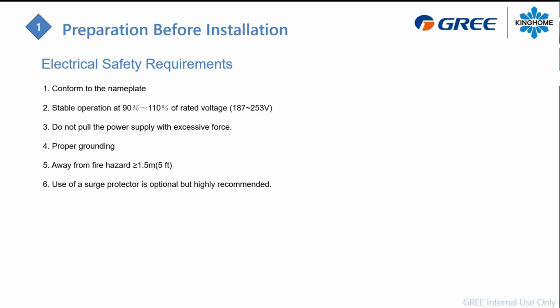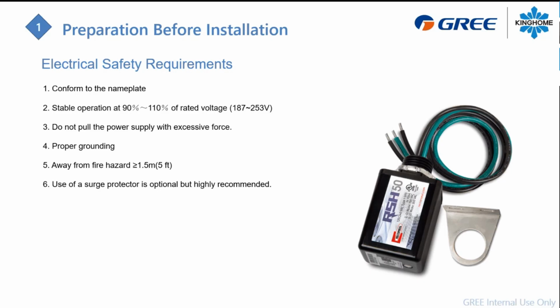Always make sure you have proper grounding also. This is very important. And the use of a surge protector is highly recommended too. You have a lot of electronic boards inside of that unit. The house can be hit by a lightning strike, something that can cause higher voltage. So the surge protector will prevent you from damaging a board or something like that. So just be aware that a surge protector is highly recommended on all those installations.